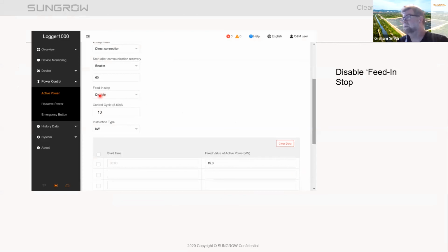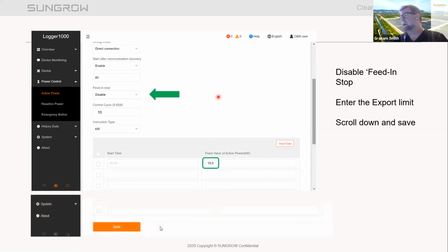and the feed in stop, disable that, because what will happen if you leave that enabled is when you start feeding into the grid, the inverter will shut down and it'll stay switched off. So you just need to make sure you disable that. And you select kilowatt instruction type and add your maximum export in here. In this case it's 15. Yeah, like that. Scroll down to the bottom and there's a save button there, and you save that. Done.